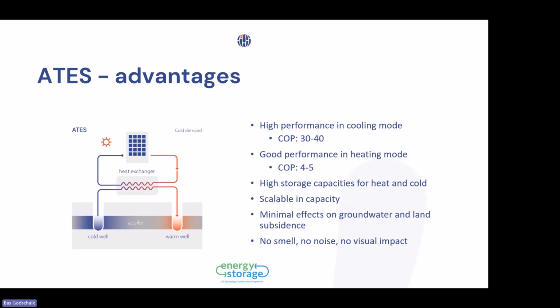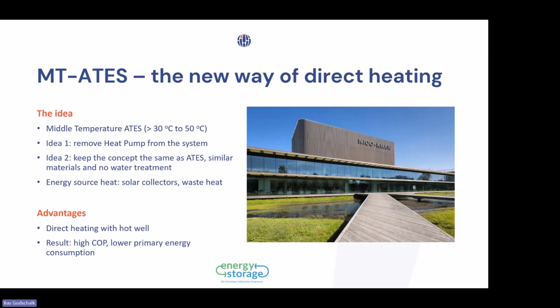So one of the ideas is, can we also improve the COP in the heating mode? And one of the clients, an ecology institute in the Netherlands, in Wageningen, NIOO, asked us, can you also think about an ATES concept where we can remove the heat pump from the system to increase the efficiency? And that's where the idea was created of the middle range temperature ATES systems, where we store higher temperatures from solar collectors and waste heat in the subsurface. And then we could abstract it at a temperature of about 50 degrees and use it for direct heating of the building. Now, in that way, we have a much higher COP because we don't need a heat pump for the heating mode.